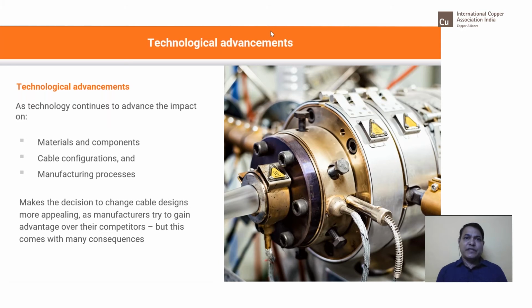The changes made to cable design based on technological advances impact the likelihood of electrical, mechanical or thermal failures in cables. Technological advancement means, what I mean to say here, is that people tend to change the raw materials to reduce the cost, and that really has an impact, so unless the design or the process is changed, it should be carefully considered and type tested again when the material is changed. If you change any material, your existing type test becomes invalid. So that is one of the reasons this slide is a very important decision that someone has to make. If you change the material, you need a new type test to confirm that the newly used or developed material meets the requirements in operating conditions by doing a stringent type test.